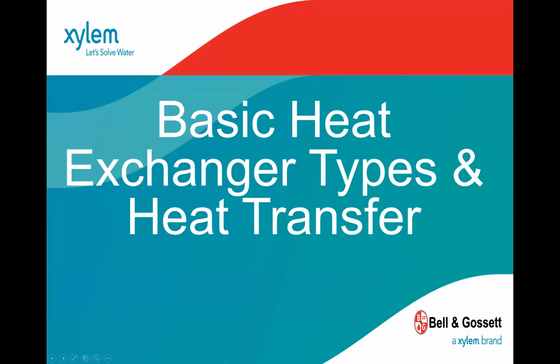Now, it doesn't apply to all applications. It doesn't apply to shell and tube. It doesn't apply to brazed plate. It doesn't apply if the system is only glycol. There's a lot of things that technically do not require AHRI 400.